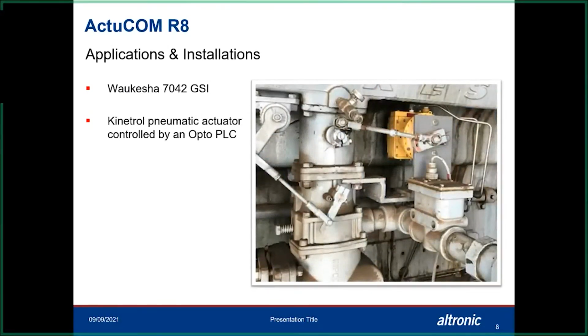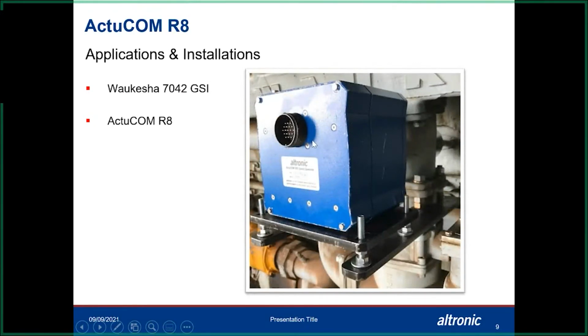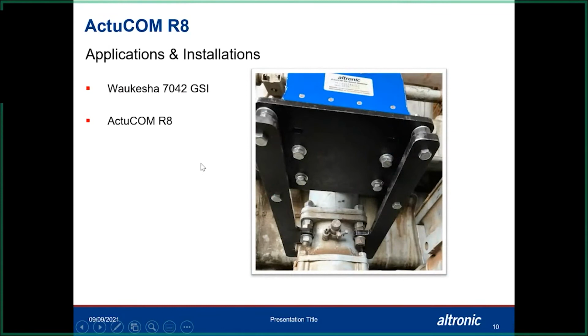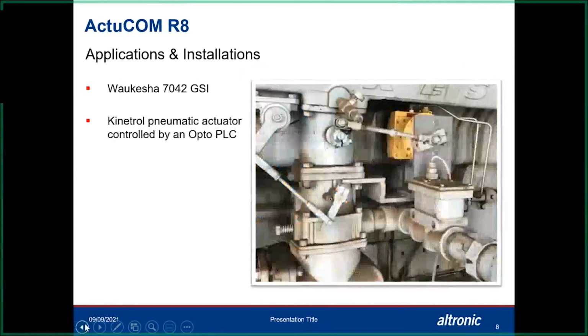This is on a Waukesha 7042. We had a PLC on this that we put on many, many years ago, about 25 years ago, that would operate a Kinetrol actuator to control the speed. With the PLC, basically we had to run it through an I2P, and then the I2P ran to the actuator, and then we control the speed. It worked pretty good. But we turned around, we put this ActuCom on, we got rid of the I2P, we got rid of the air signal going to it, and plus we got rid of that little bit of linkage that was back there. Because we had all of this linkage right here that, like I said, is still maintenance with all your Heinzmann joints and all that stuff.